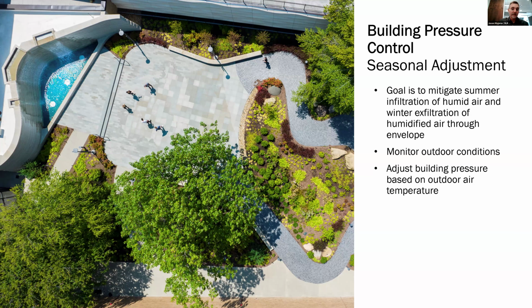So you've got to be careful with that. And one way to mitigate that is to have a seasonal adjustment in your control sequence. What we did in our control sequence is monitor outdoor air temperature. We picked a conservative number, and when the outdoor air temperature dropped below it, we adjusted our building pressure to a neutral or slightly positive set point. For pressurization, we program an offset between outside air and relief air, but we make that dependent on that outside air temperature variable.